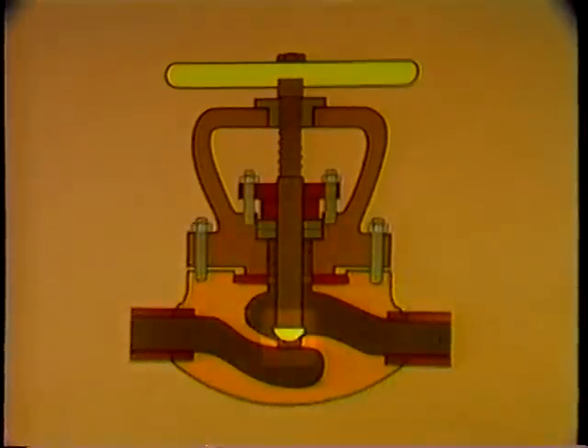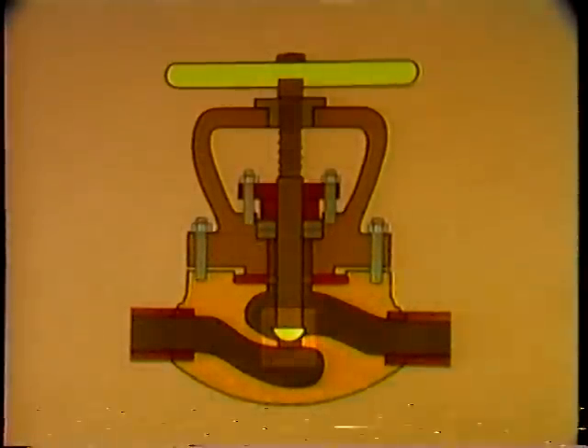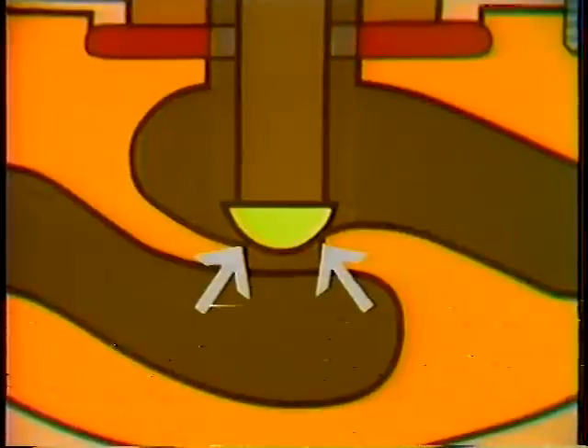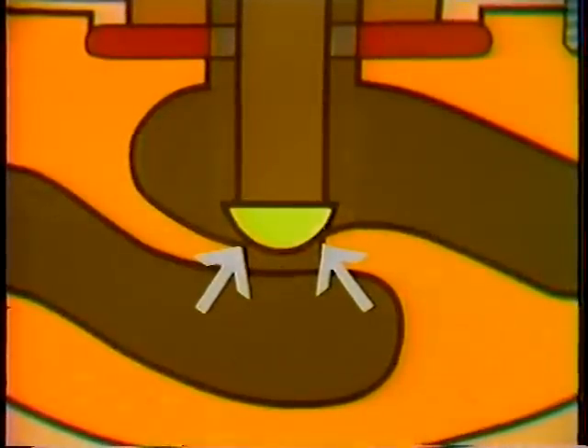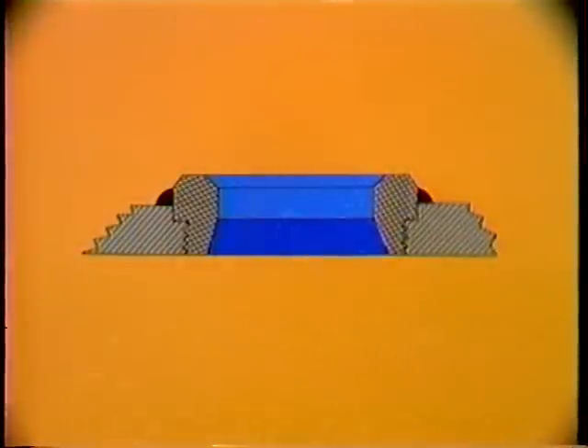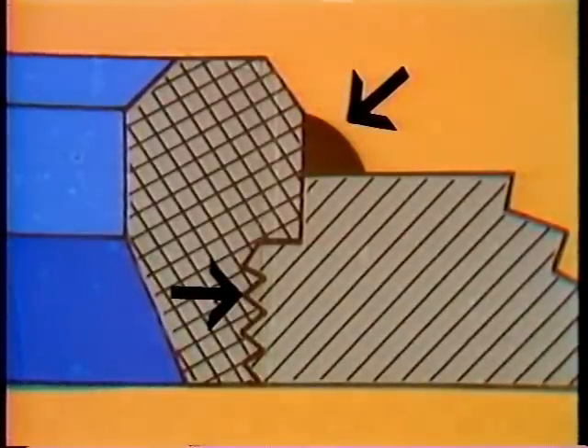Inside the valve body is the seating area. The seat is a stationary part of the valve — it is here that the disc closes on the valve body. The areas where the disc and seat come in contact must be smooth and fit perfectly to completely stop the flow of fluid or gas through the valve. The seat is often threaded or welded into the body of the valve. In high temperature, high pressure systems, a combination of threading and welding is used to prevent leakage between the valve body and seat.